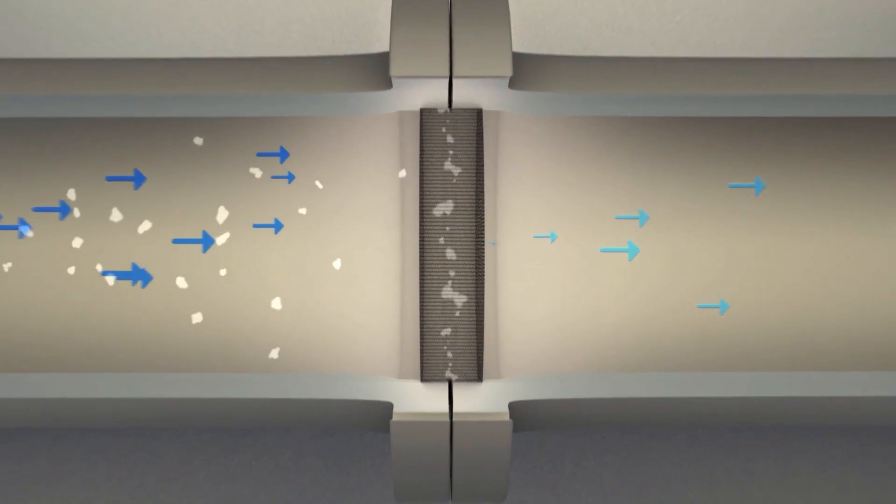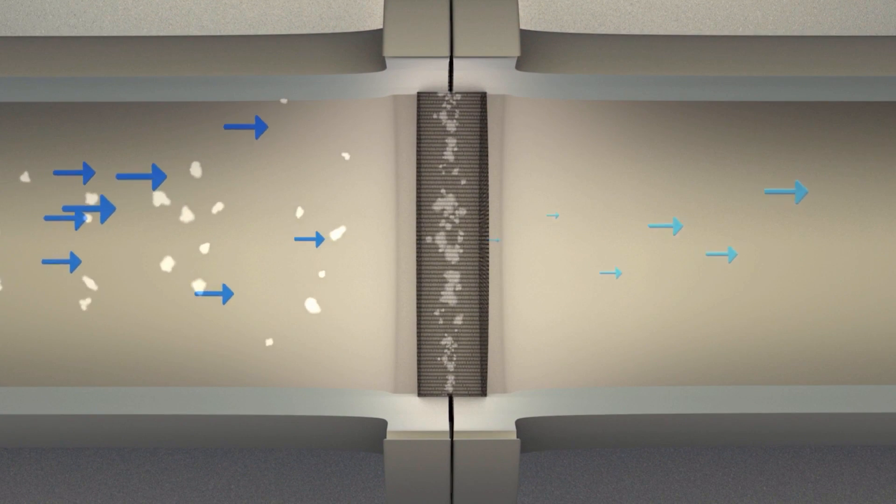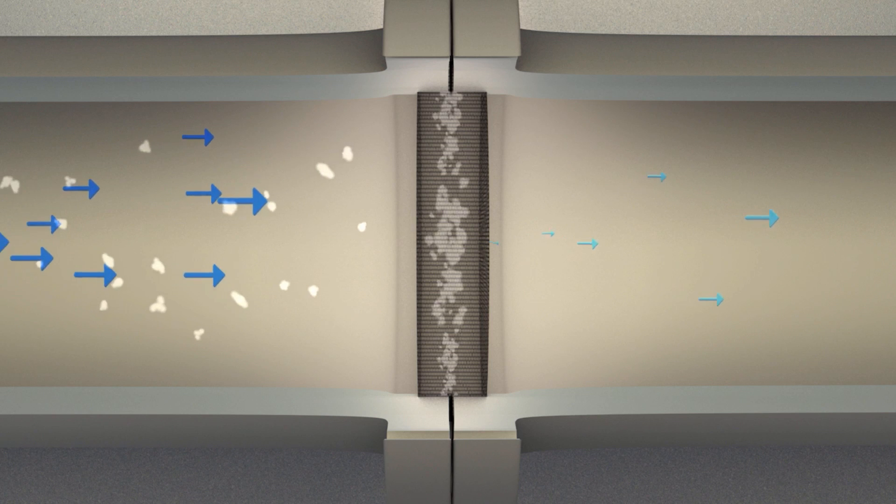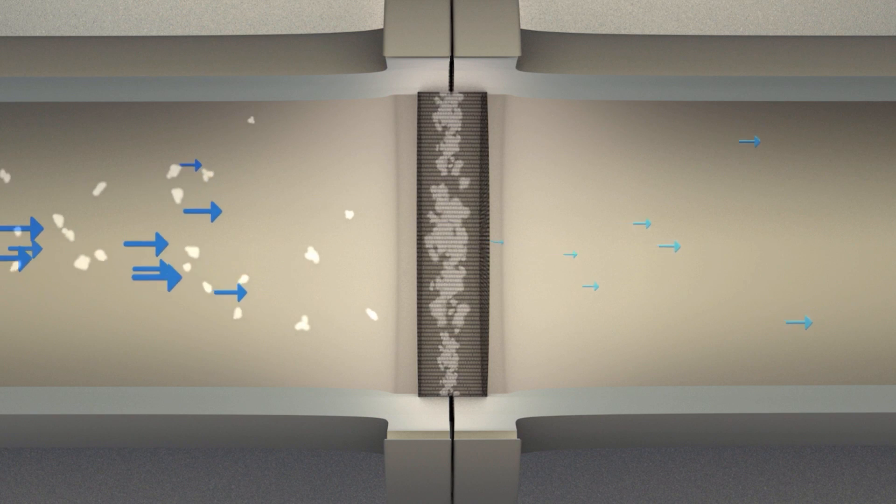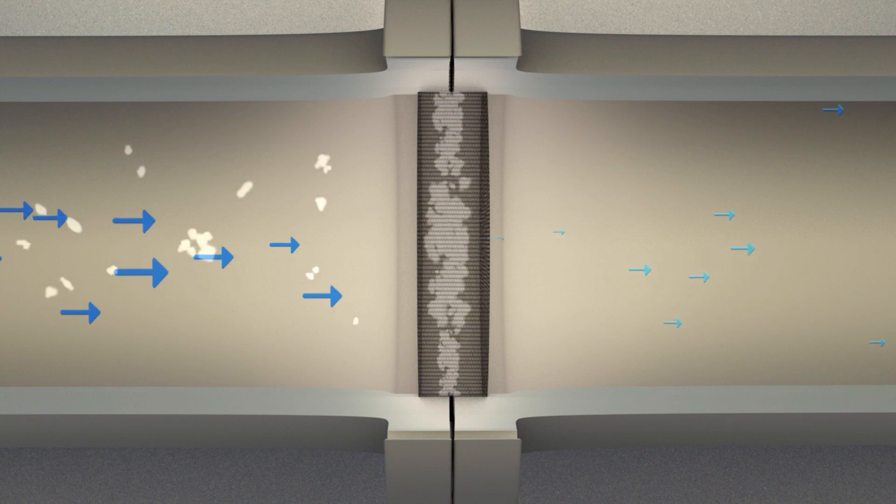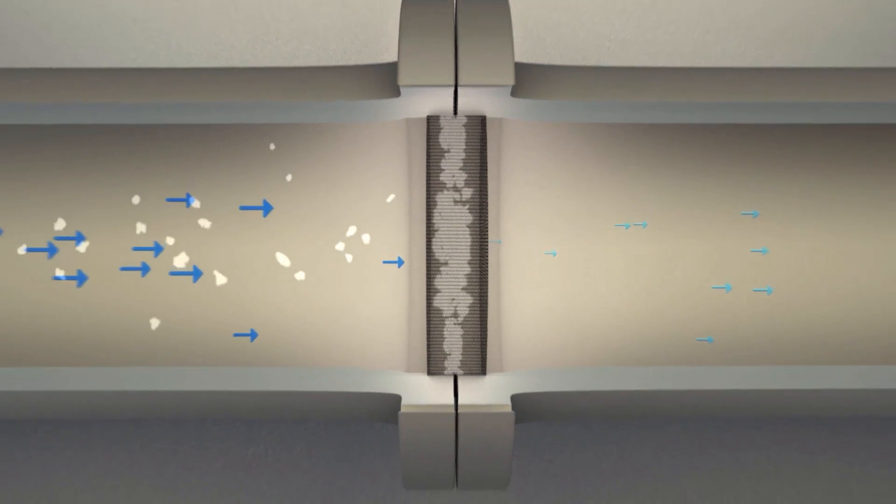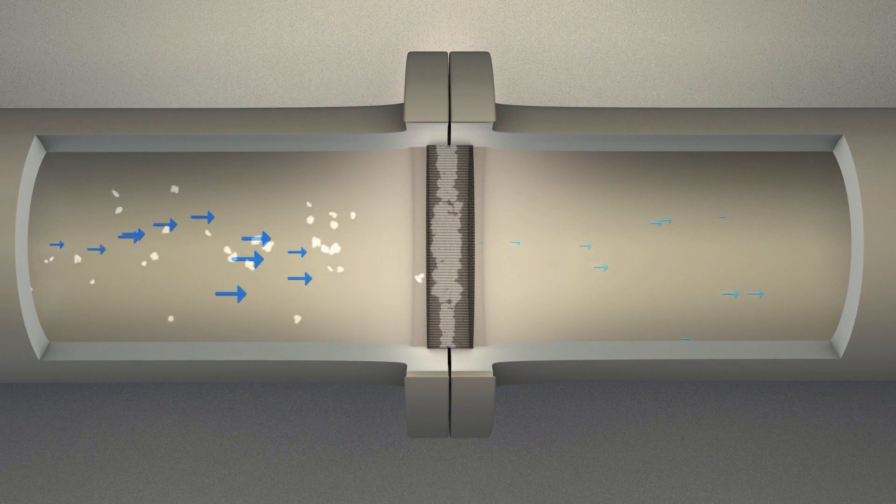Contaminants or particulates that build up in the filter will reduce media flow. As the filter becomes clogged, the downstream pressure drops. This results in an increased differential pressure, also referred to as the delta P or DP.